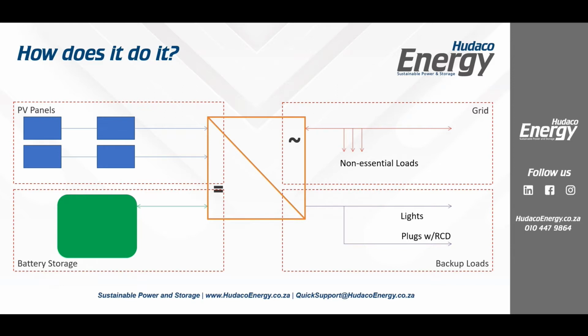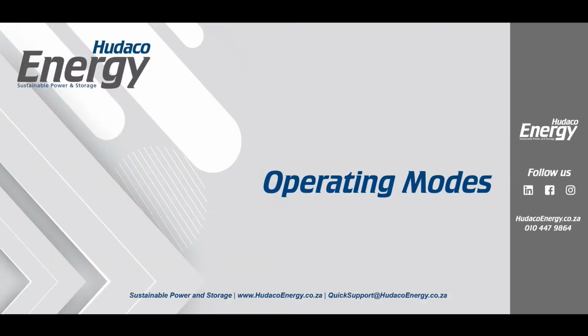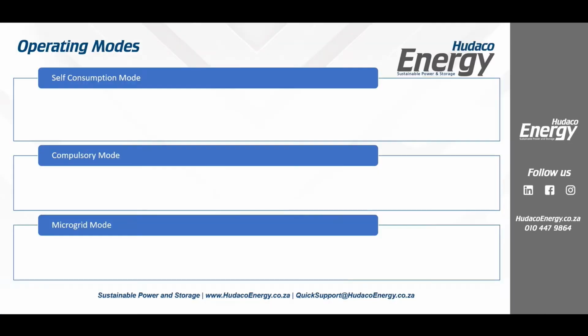Perfect. Okay, so let's talk about now the different operating modes that we do have available to us. In the inverter, when you're doing the setting up or when you're doing the analysis, you'll actually find that there are quite a few different modes of operation. I think there's a total of 7. 4 of them we don't use. I think one's for Italy, one's for Australia. A couple of others are for much more advanced settings that we're not going to use. We are really going to focus only on 3 modes: either self-consumption mode, compulsory mode, or microgrid mode.